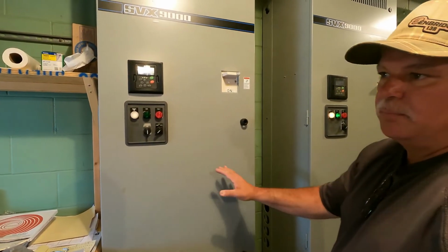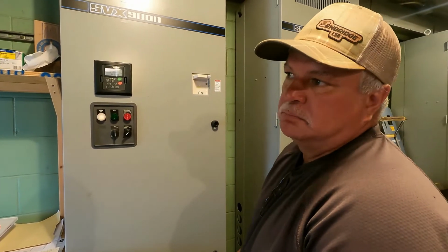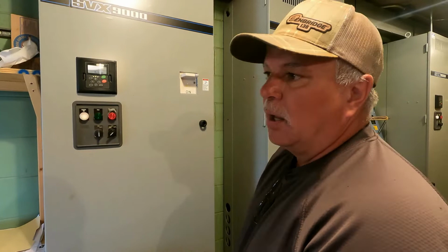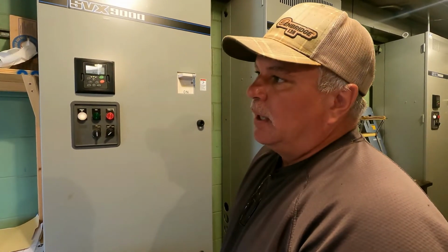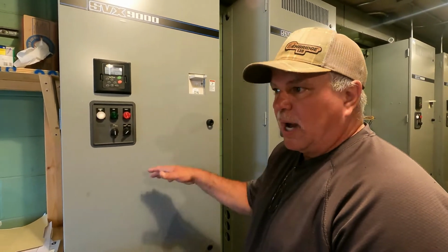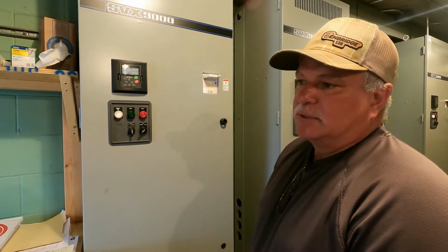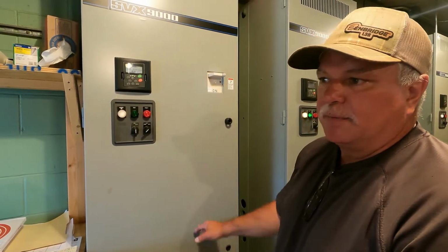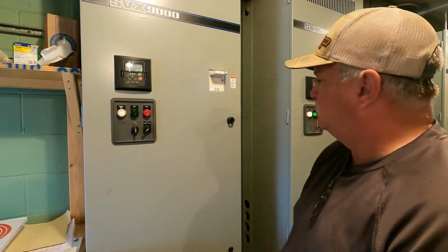So these will go down just about from 200 gallons a minute at the minimum, all the way up to approximately 2,500 gallons a minute at the maximum. And then there's a backup float system. If it goes more or higher than that, the backup float system would tend to kick more pumps on and off if there was problems with the inverters.